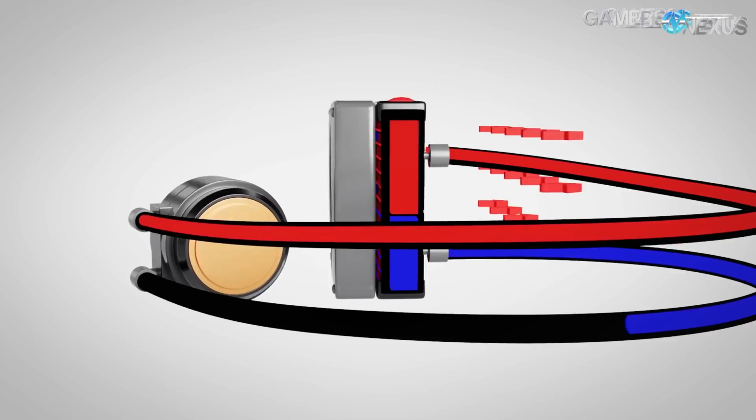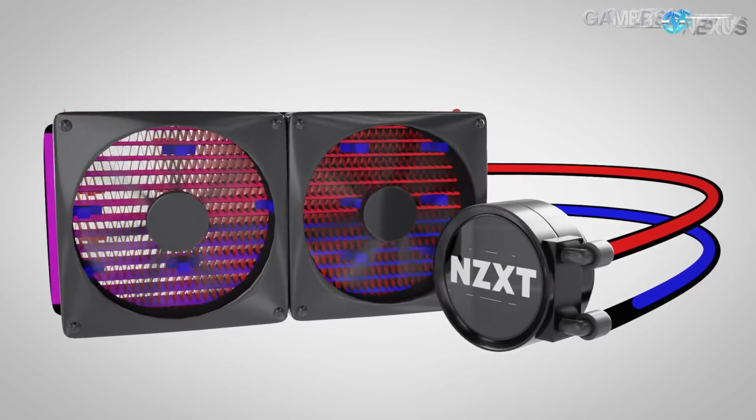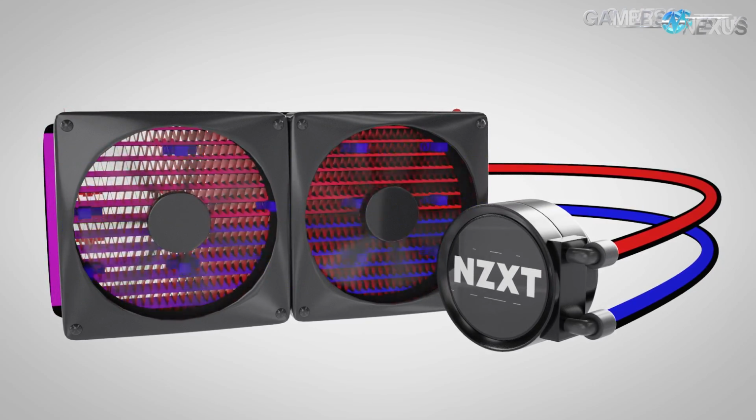But a lot of people think that the units die or fail in a similar way that a fan or a hard drive would. A lot of end users, and even IT administrators in big data centers, look at components split up. You have your solid state components, and you have your rotating, moving, bearing-containing components, and those would be your fans and your hard drives, and they like to think that liquid coolers are in that group as well.